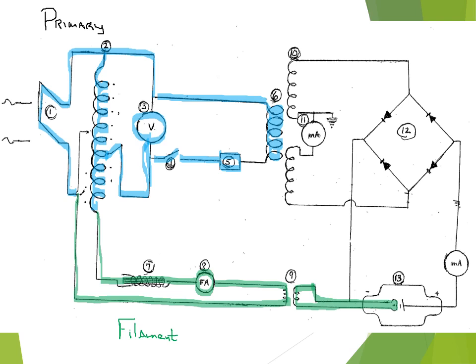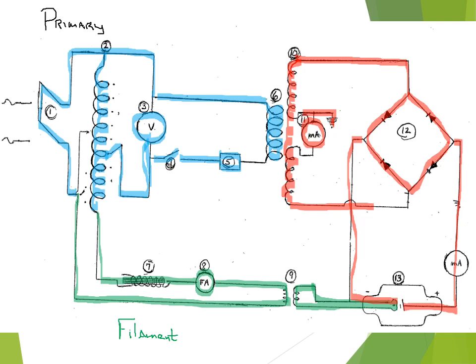And then we have the third part, which is the secondary side. So we're going to talk about 10, which is the secondary coil of the high voltage transformer. We're just going to close that gap there. It includes the number 11, which is the MA milliammeter. It has a ground wire, by the way. It has number 12, which are the rectifiers. And then it includes the cables coming down and going through the X-ray tube. Okay, and that is the secondary circuit.